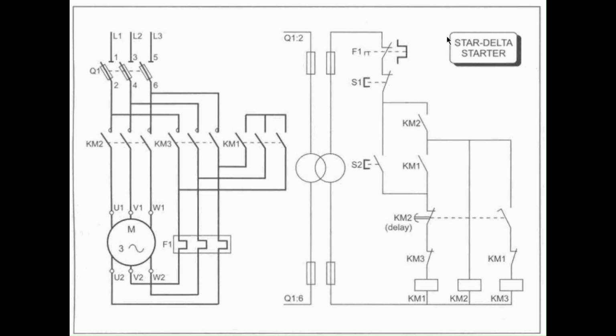Another common question in the Officer of the Watch exam is please explain a star delta starter. So here we're looking at a star delta starter. We walk through the circuit. We have a fused circuit breaker, three sets of contactors, the motor and the overcurrent relay. And then on the control side, this is the supply voltage, which in practice is usually taken off around here.